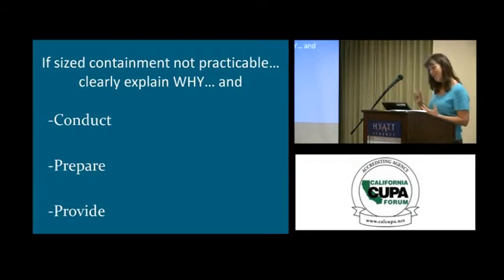I was a little unclear on this when Pete and I were putting together this presentation, on whether a qualified facility that is preparing their plan can do an impracticability determination. What he explained to me earlier this week is that if it's a qualified facility and they're doing their own plan, they could still self-certify the plan, but just for the impracticability determination, they would need to have a PE certify that impracticability and alternative means and put together that portion and certify that part of the plan.